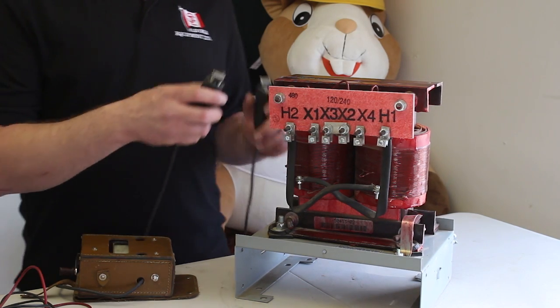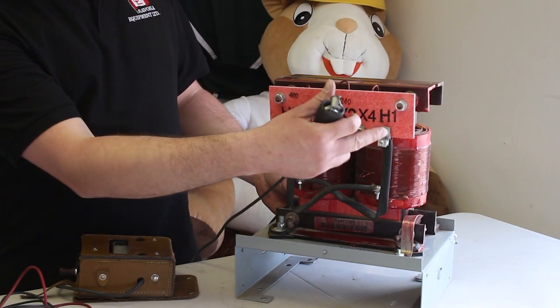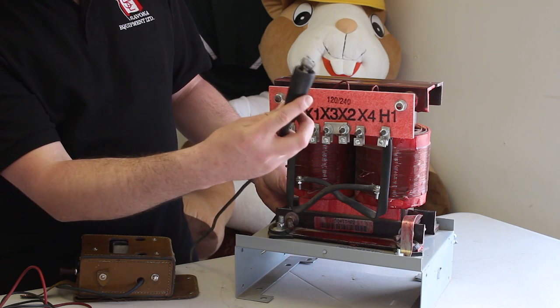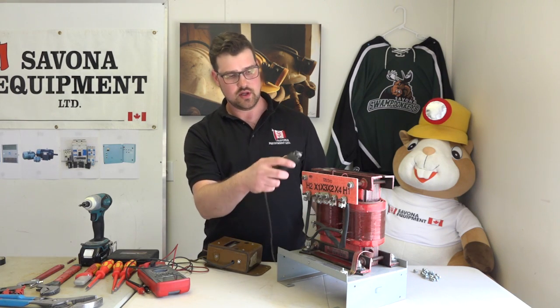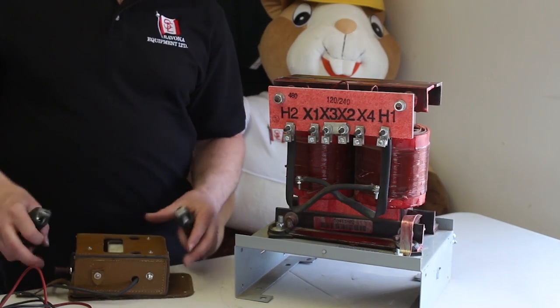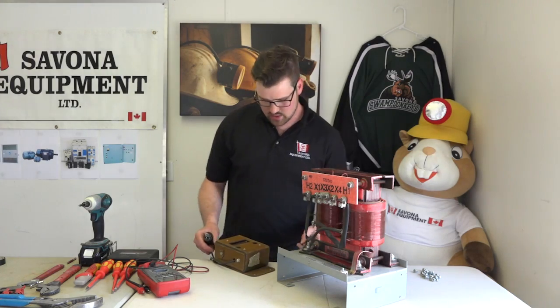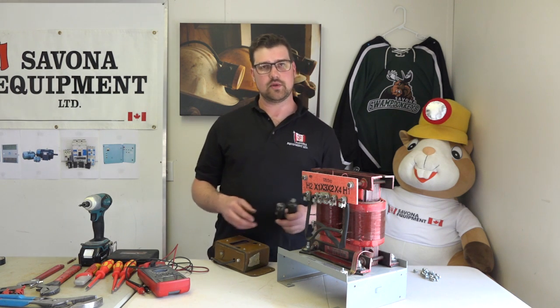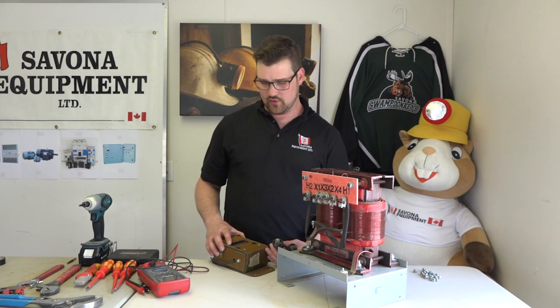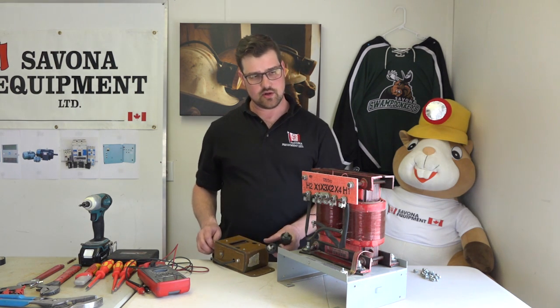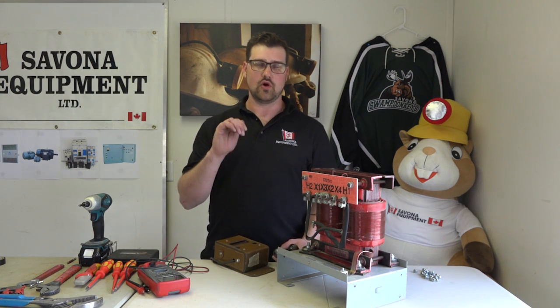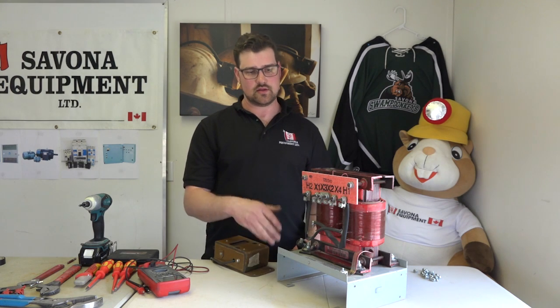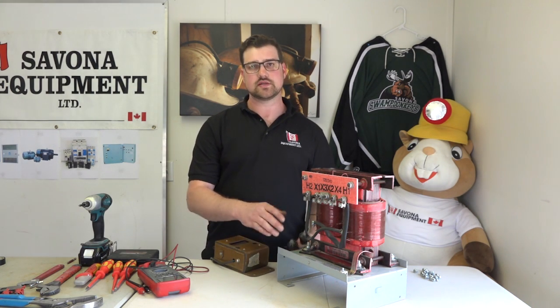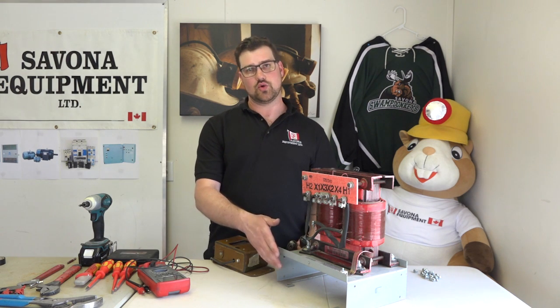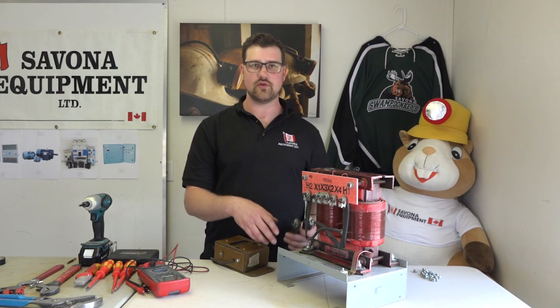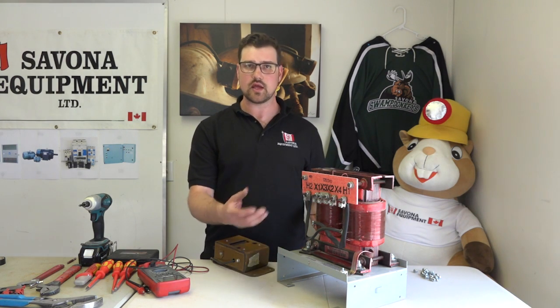Okay, so next we're gonna megger the transformer, and I'm gonna do this by meggering from the high voltage winding to the low voltage winding, and then high voltage winding to ground, and low voltage winding to ground. And so we have an old wound type megger here. So when you're meggering a piece of equipment, you're testing the insulation. What you want to look for on your meter is, as you're meggering this piece of equipment, you want to see the ohmic value increase. That's when you know that it's a good piece of equipment. If it decreases as you're meggering it, that means that you have a short somewhere in the winding, or if you're doing a piece of cable, there might be a short in the cable somewhere.